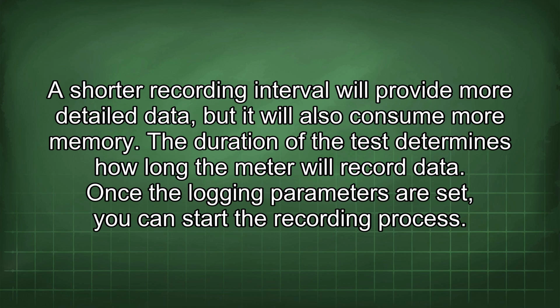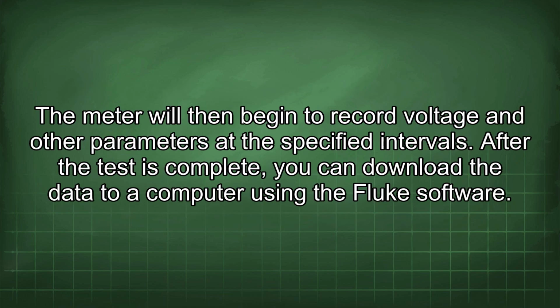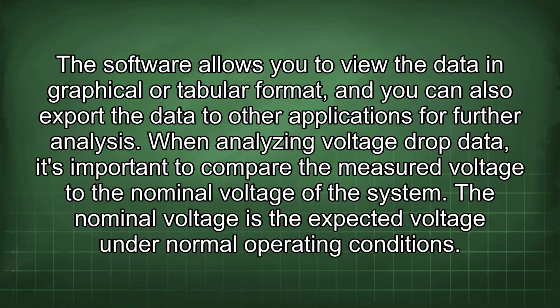Once the logging parameters are set, you can start the recording process. The meter will then begin to record voltage and other parameters at the specified intervals. After the test is complete, you can download the data to a computer using the Fluke software. This software allows you to view the data in graphical or tabular format, and you can also export the data to other applications for further analysis.